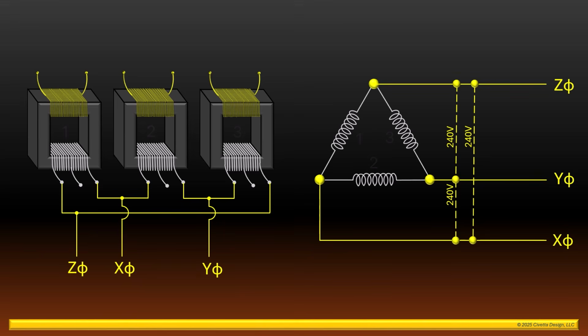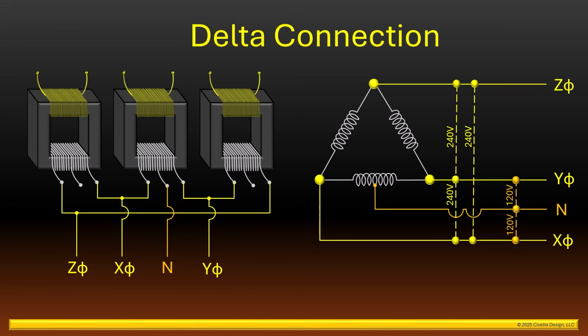Also, if you recall, these transformers have a center tap position. If we connect a fourth lead to the center tap of the middle transformer, this becomes the neutral. Shown on the right, the neutral creates a voltage potential of 120 volts between the X phase and the neutral, and also between the Y phase and the neutral. This is also referred to as a delta connection.